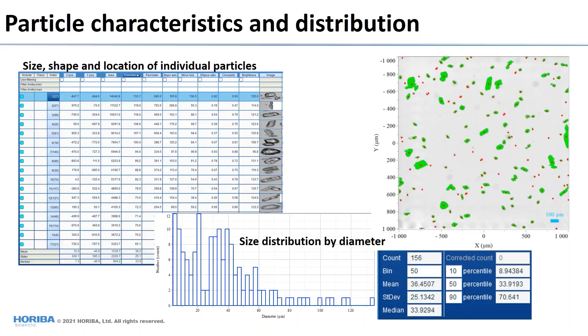The advantage of having access to individual particle characteristics is that when you have outliers or suspect particles, you can go back and examine their ellipse ratio or circularity, look into what's going on in your sample. And because you have the location, you can pick out that outlier particle for additional analysis as well.